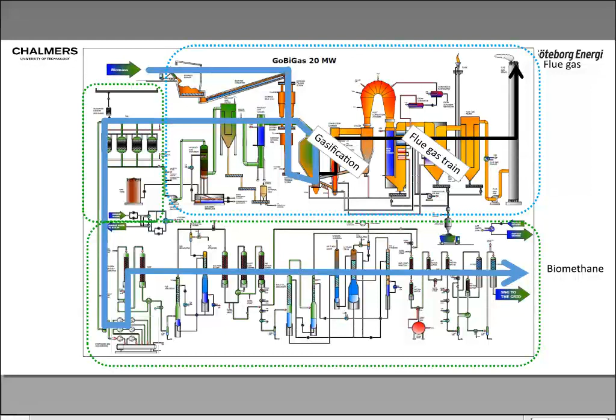It turns out that to build a commercial plant, it is required to have more than one gasification unit. This is due to the maintenance interval, which proved to be between 12 to 18 months. This is very similar to what is normal in the forest industry. Whereas the methanation unit has a longer period of running before we have to have a maintenance shutdown, around 48 months, very similar to a petrochemical industry.